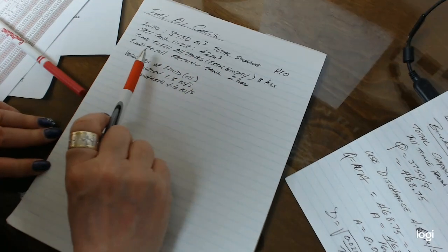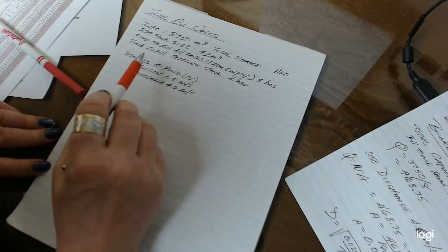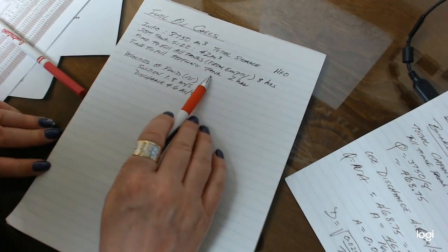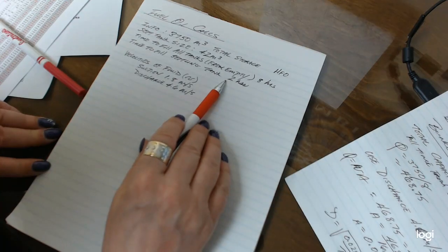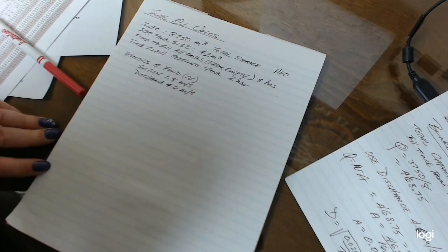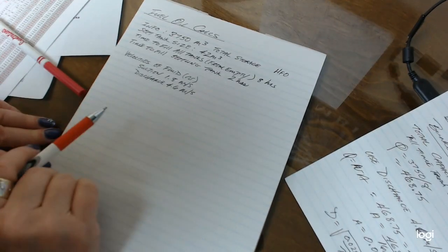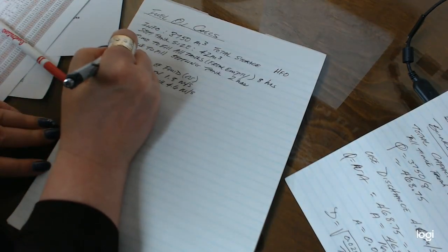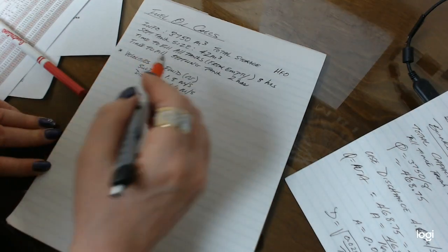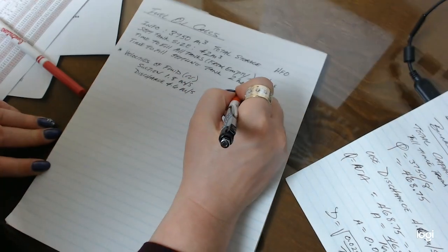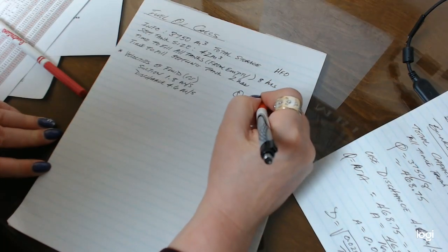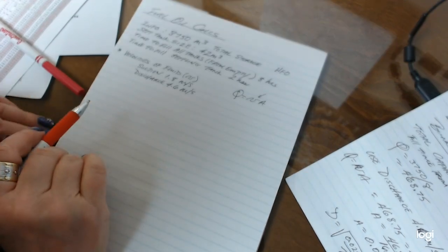And the last little piece to give you information on now is the time to fill the settling tanks. If you remember from class, I had mentioned that this could take anywhere from a half hour to 2 hours. I'm using 2 hours as a point of convenience. Now, one of the things I want to highlight is that when we do these calculations, you have to look for the velocities of the fluid you're using. When we look at the formula, Q equals VA, the V I'm looking for is the fluid velocity.